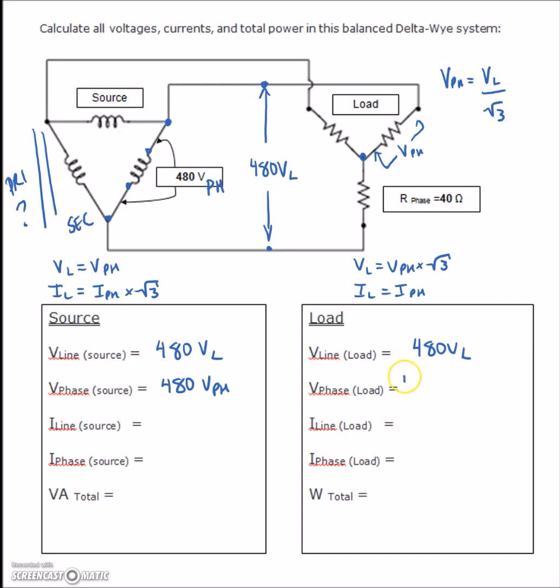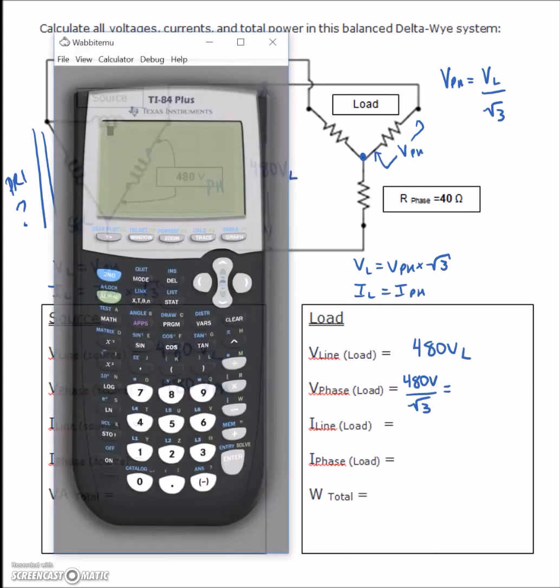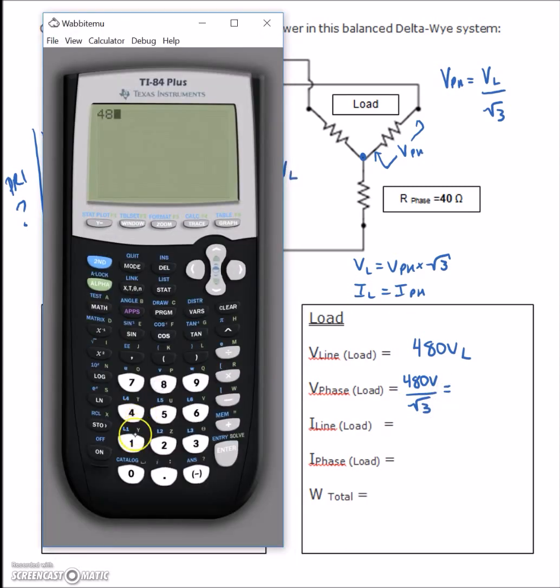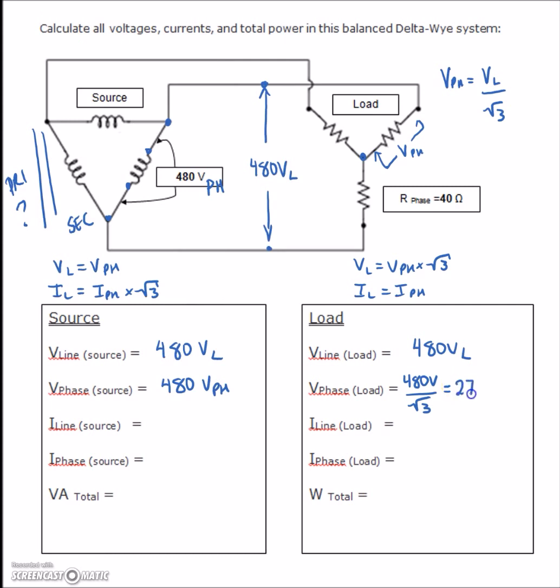V_phase = V_line ÷ √3 = 480 ÷ √3. Putting that into the calculator gives us 277.12, so we round to 277V on the phase.